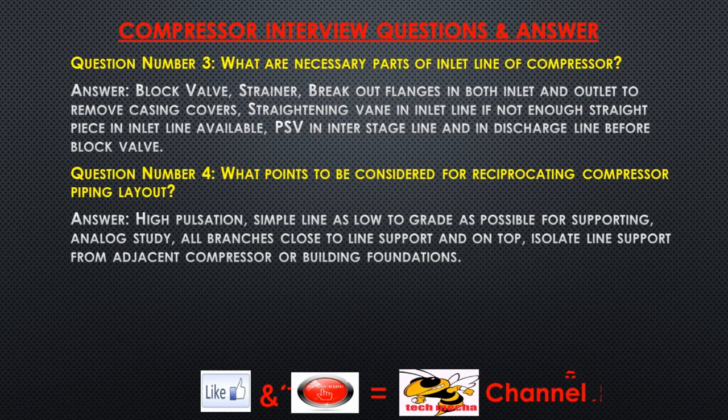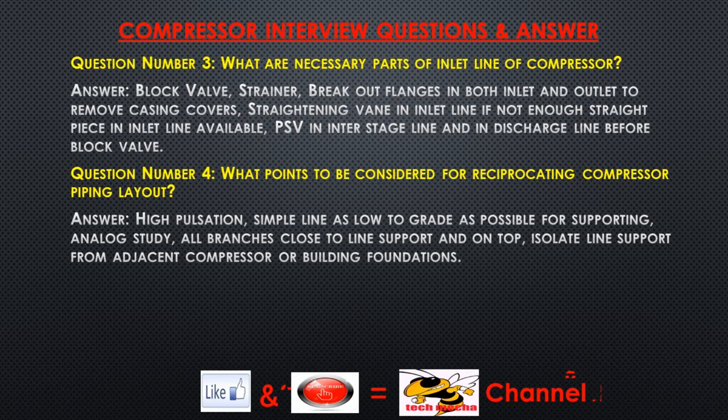Question number 4: What points should be considered for reciprocating compressor piping layout? Answer: High pulsation, simple line as low to grade as possible for supporting, analog study, all branches close to line support and on top, isolate line support from adjacent compressor or building foundations.